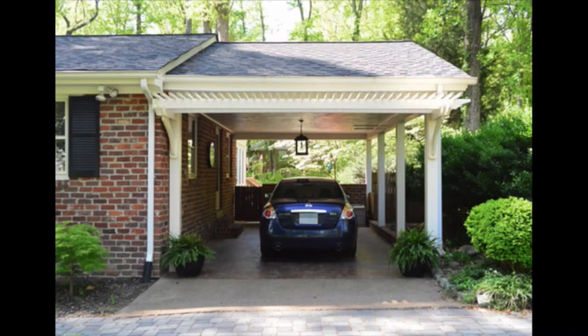Okay. Now, are they mandatory for homes that have an electric fireplace but no garage? No. Houses that don't have fuel burning appliances and do not have an attached garage then have no source of carbon monoxide. Okay, so is a carport considered a garage? No, a carport's not a garage because it's open on the various sides, so the air flows through, so there's no opportunity for carbon monoxide to be trapped inside.